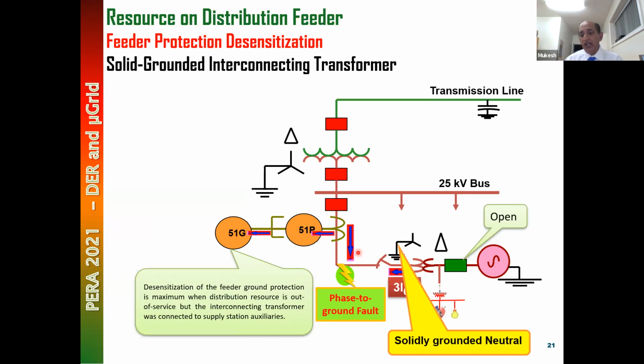Basically, instead of doing a solid, actually, I want to make one more point. You will be surprised. This is where you learn when you work in a utility. The desensitization is actually worse when this circuit breaker is open. That means when this generator is not operating. Why is it worse? Because this transformer acts as a source of zero sequence current. The fault current comes here, and also it flows into this path, and it circulates through this delta. Actually, I'll show you a record.